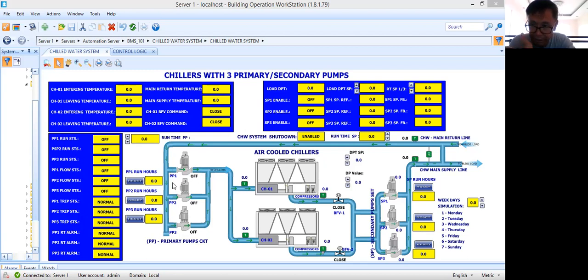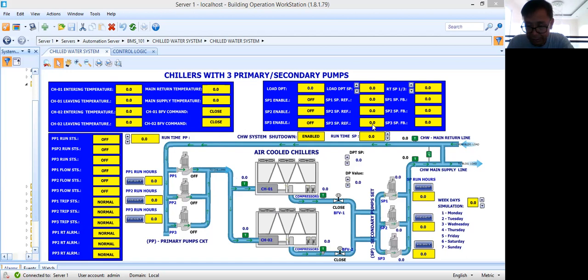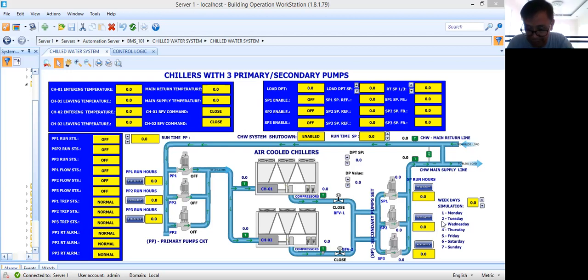Runtime alarm is the accumulated run hours. We have here the runtime set point for the primary pumps, and also for the secondary pumps. This runtime is already for maintenance purposes. For the secondary pump, it will be controlled by the differential pressure transmitter installed across the chilled water main return line and supply line. We will have a low differential pressure set point — this will dictate how many pumps should run and what the speed reference will be. The setup will be two duty, one standby for secondary pumps. Likewise for primary pumps, it could be two duty, one standby.